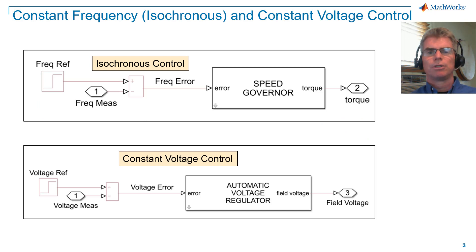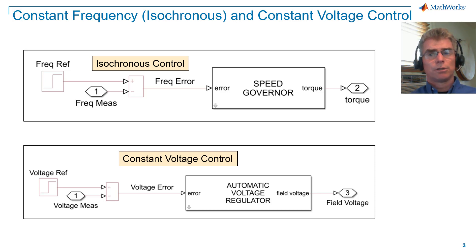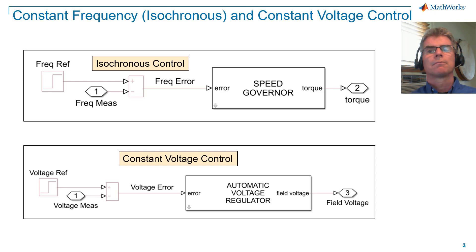Before we dive into droop control, I'll first set some context by discussing constant frequency and constant voltage control. Note that constant frequency control is also referred to as isochronous control. Isochronous control means a generator unit will regulate frequency to a given setpoint, regardless of the active power output of the generator. Constant voltage control means a generator unit will regulate terminal voltage to a given setpoint, regardless of the reactive power output of the generator.